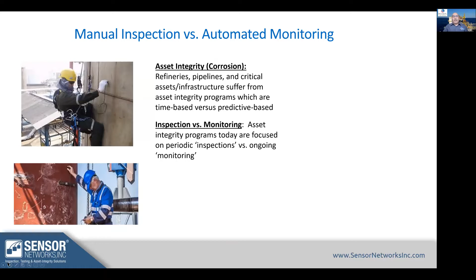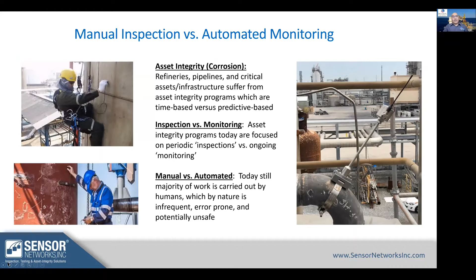For more than 100 years, internal thickness inspection has been based on human activities — early on by shutting down equipment and doing close visual inspection, later by manual ultrasonic testing. So it has been time-based inspection instead of prediction-based. That continues today, with integrity programs based on periodic inspection versus ongoing monitoring. But this mentality should be abandoned, as manual UT monitoring is by nature sporadic, prone to errors, potentially unsafe, and we now have superior systems that can overcome these limitations.